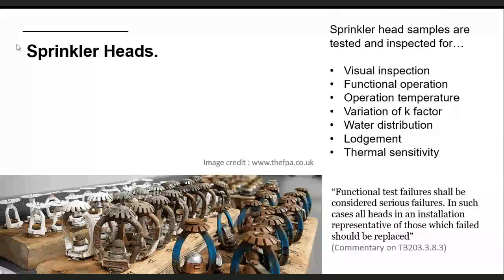Do they function as designed? Is there any damage to the heads? They'll also look at the K factor, which is listed on the head. Is that K factor actually still good? They'll check all of that. And then there are various points in Technical Bulletin 203 which will determine whether the results are a pass or a fail. Obviously, if all the tests are good, then there's no need to do any further action.